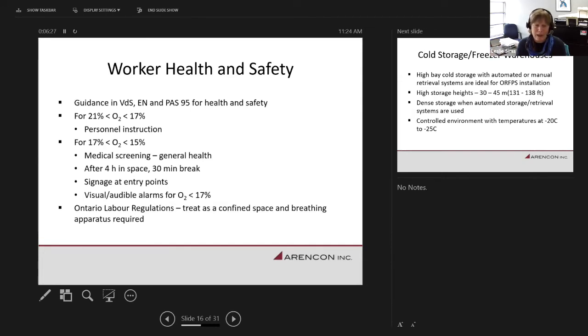And we have alarms that trigger if the oxygen level goes below 17%, to warn people that the system has gone below the prescribed level of 17%. So this is how they manage it in Europe. But when we get into an installation in Ontario, in Canada, or within North America, we're dealing with labor and workplace safety, and Ontario Labor will treat these as confined spaces, I think at below 19%. If you're entering a space at below 19%, breathing apparatus is required.